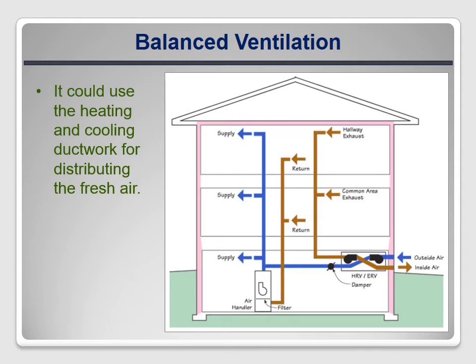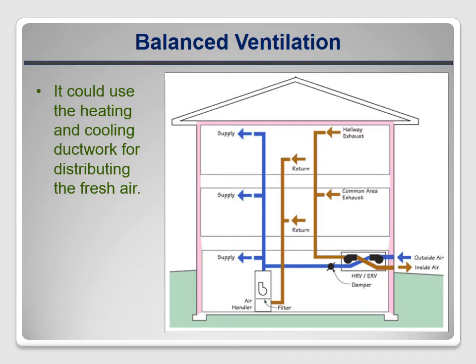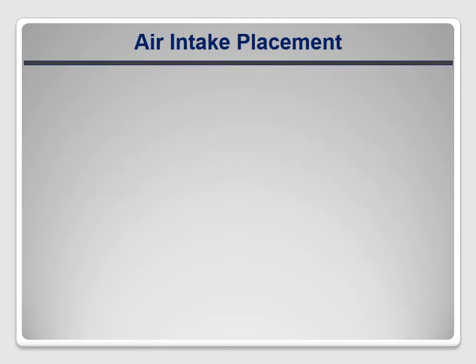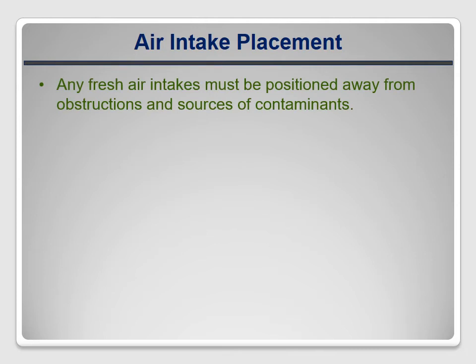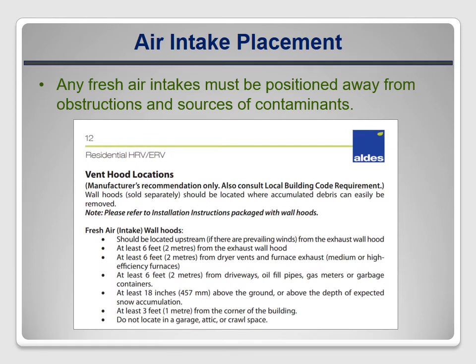As you can see, there are a lot of ventilation system options. Hopefully this summary will give you a good framework to start doing research for your projects. Any air intakes into supply-only or balanced systems must be installed in locations that avoid obstructions like snow or plants, and they must be kept suitable distances from sources of contaminants like exhaust outlets and combustion appliance vents. Here are the instructions from an HRV and ERV installation manual. The ASHRAE requirements are even more restrictive — take a look at section 6.8 for more details.